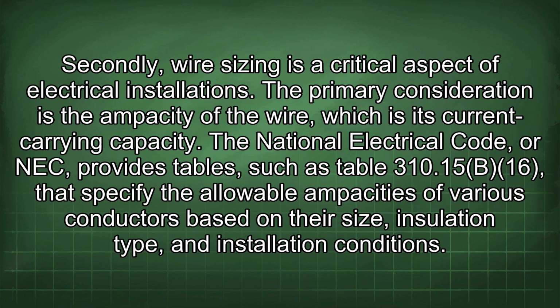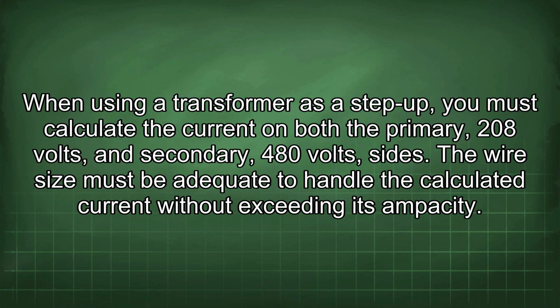The primary consideration is the ampacity of the wire, which is its current carrying capacity. The National Electrical Code, or NEC, provides tables, such as Table 310.15(B)(16), that specify the allowable ampacities of various conductors based on their size, insulation type, and installation conditions. When using a transformer as a step-up, you must calculate the current on both the primary, 208 volts, and secondary, 480 volts, sides. The wire size must be adequate to handle the calculated current without exceeding its ampacity.